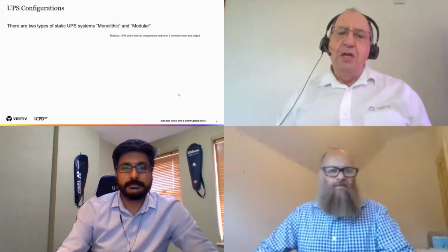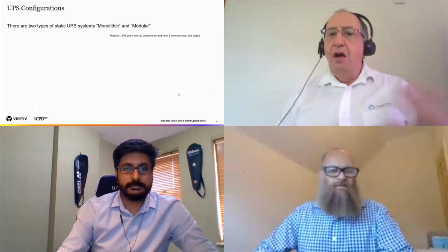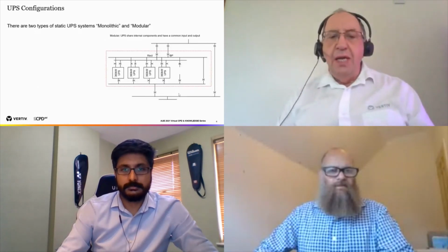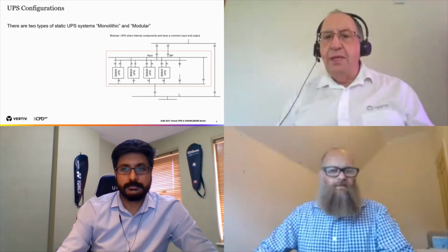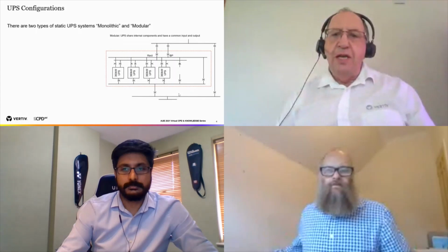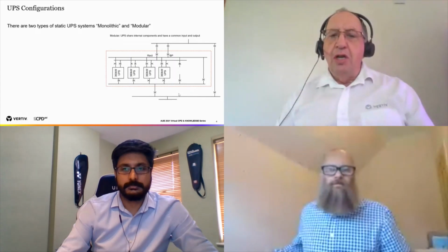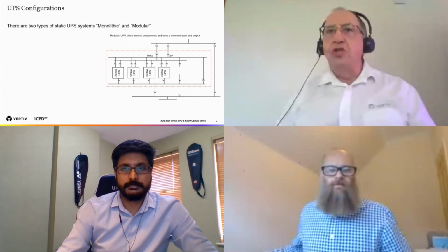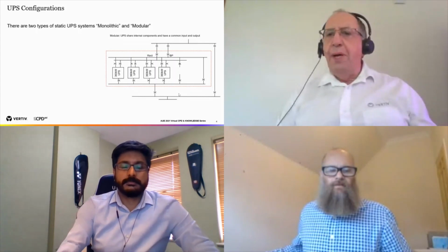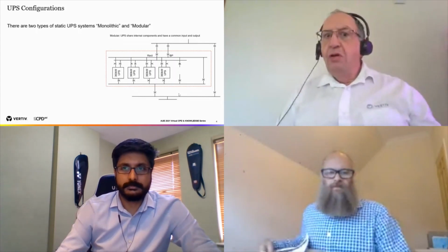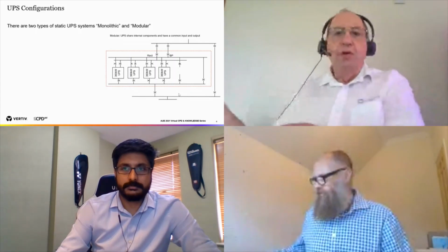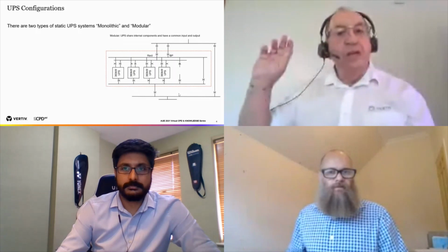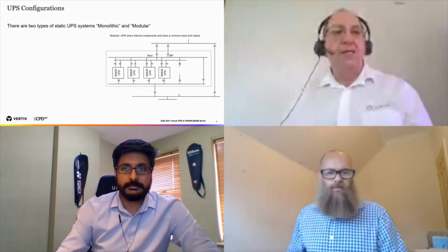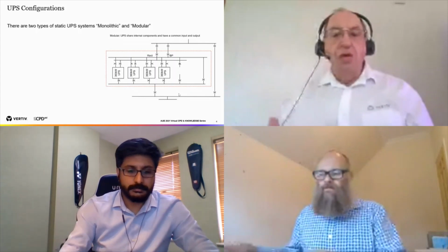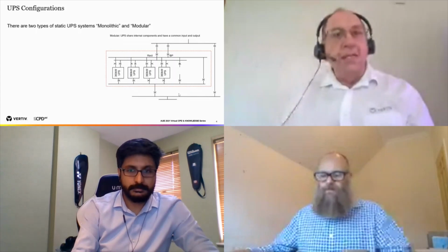There are two basic types of static UPS. We've got monolithic and modular, and there are benefits and pros and cons for each. So modular tends to be a unit with a busbar system inside. So the red dotted line shows the UPS, and those modular UPSs can be slotted in and out to suit load conditions. So you might have a load on one part of a campus that is going down. So you could take the modules out of that UPS, walk them across the campus into another building and plug them into an identical UPS and increase the capacity in another place, for instance. That's also available on a modular battery basis as well.